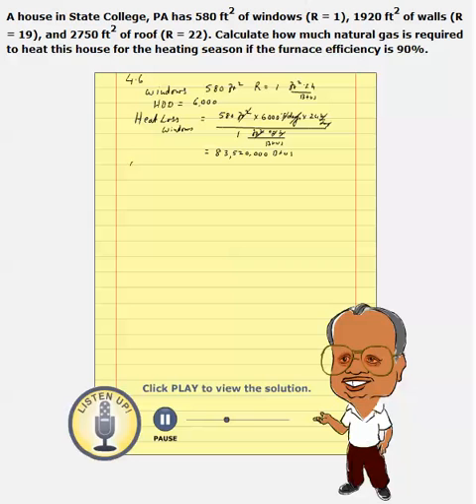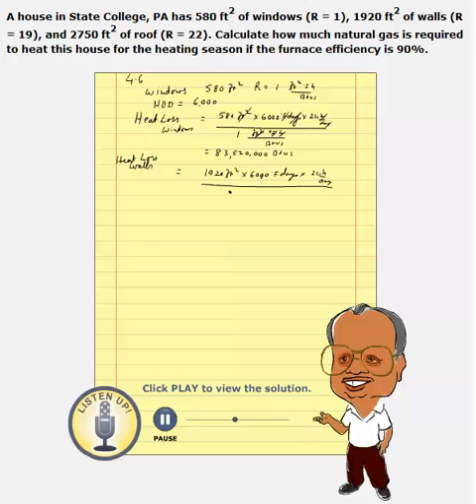Now let's calculate heat loss through walls. That will be 1,920 ft² for walls, HDD is again 6,000, and there are 24 hours in a day, divided by the R value of the walls, which is given as 19 ft²·°F·hr/BTU. Canceling units, the heat loss from the walls appears to be 14,551,579 BTUs.